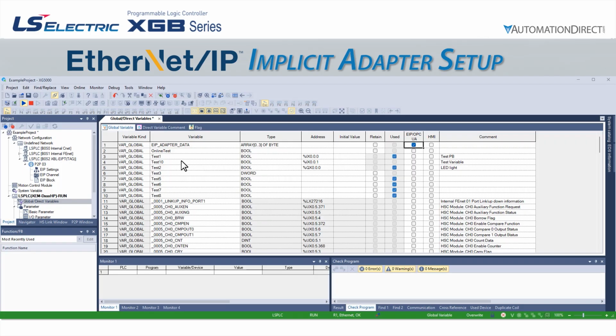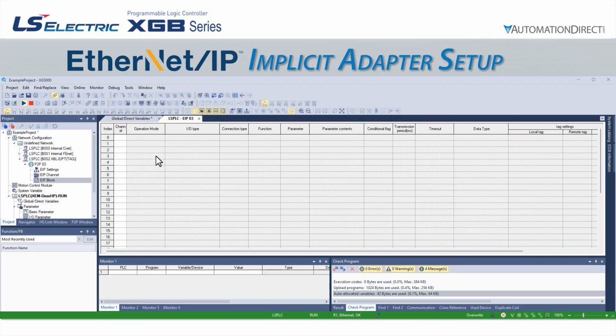Now that we have our array created, we can add this array to our implicit adapter by double-clicking on EIP block in the project window. This opens the LSPLC EIP03 window. We will set the channel to 0. We have already set up channel 0 as an implicit target, so it adds that to the operation mode.